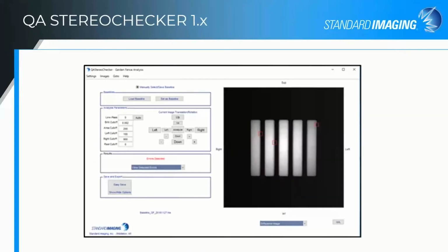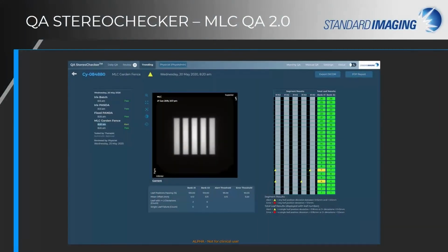From a semi-quantitative MLC test to an absolute MLC position test, the MLC garden fence test has been completely reconfigured. The MLC leaf positions are analyzed against Accuray's 4 recommended tests. 2 test criteria examine leaf positions by bank: percent of leaves passing per bank, and the mean offset for each bank. The other 2 criteria are specific to individual leaves: the number of segments where leaf position is offset by greater than 0.5 millimeters, and whether any one leaf position is offset by greater than 0.95 millimeters. Hovering over a leaf tab will display the expected position, the actual position, and the deviation from expected.